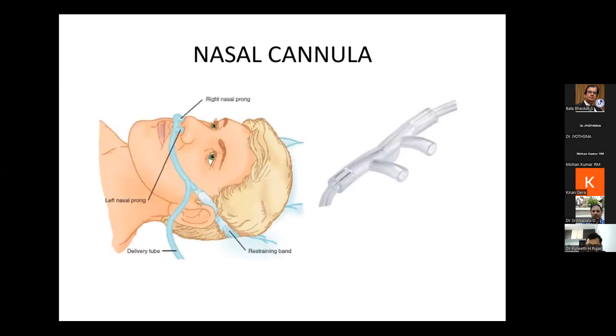So we have a variety of nasal cannulas. The nasal cannula consists of two soft prongs attached to an oxygen supply tubing. A flow rate of 2 to 4 liters per minute delivers an FiO2 of 28 to 36%. So how do we calculate the FiO2 in the case of a nasal cannula? Using this formula: 20% plus 4 times the oxygen liter flow. Here there is no increase in FiO2 if a flow rate of more than 6 liters per minute is kept. In the nasal cannula, the nasopharynx acts as a reservoir for oxygen. If the patient breathes through the mouth, airflow produces a Venturi effect in the posterior pharynx, entraining oxygen from the nose.